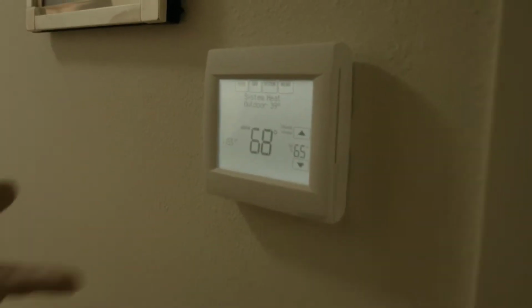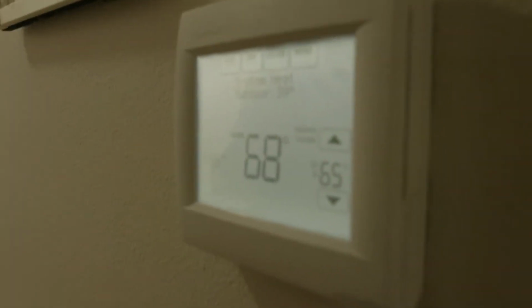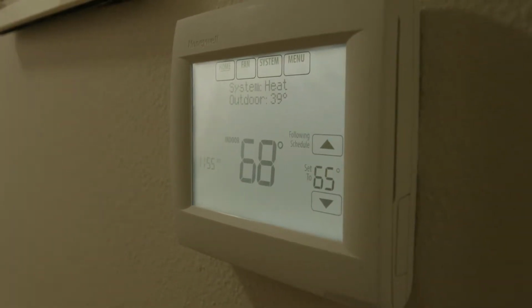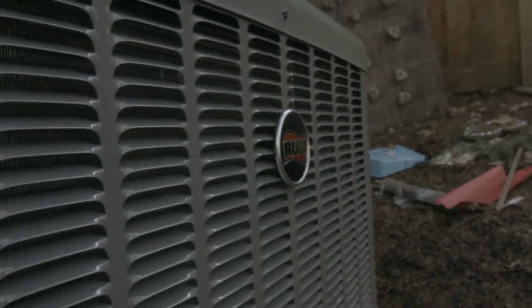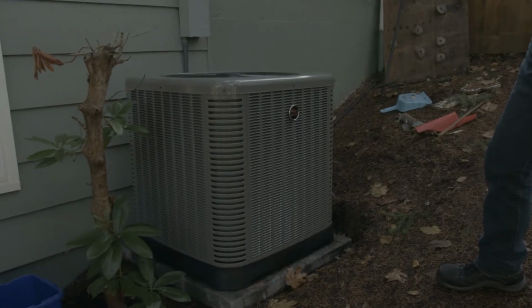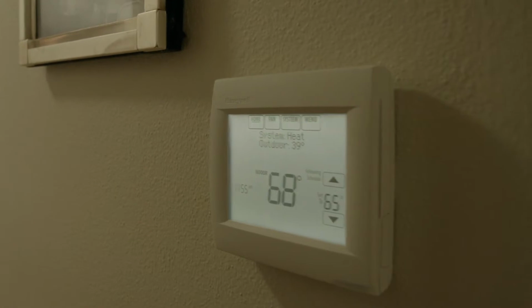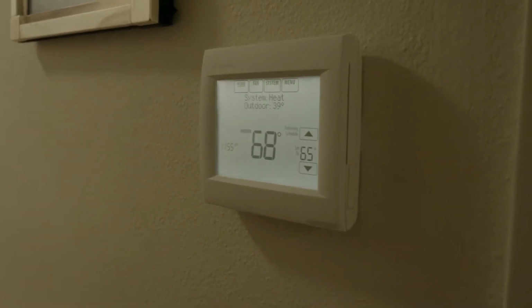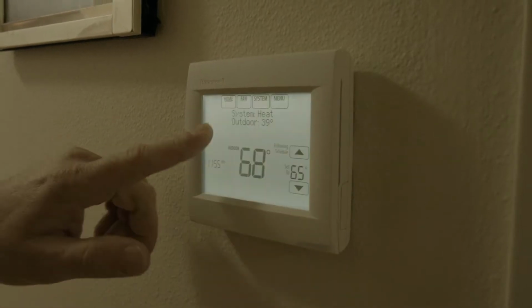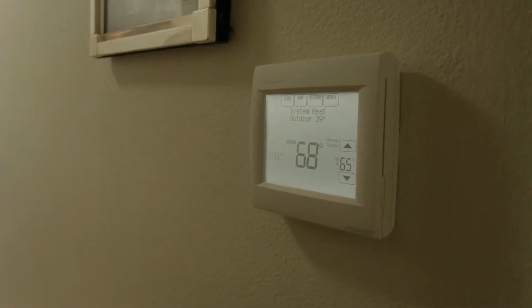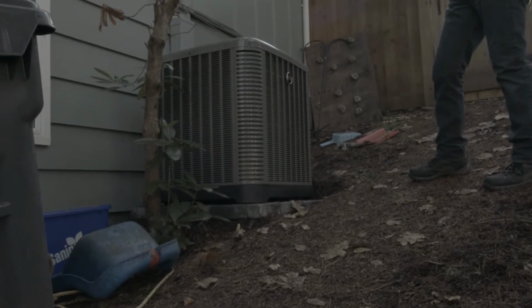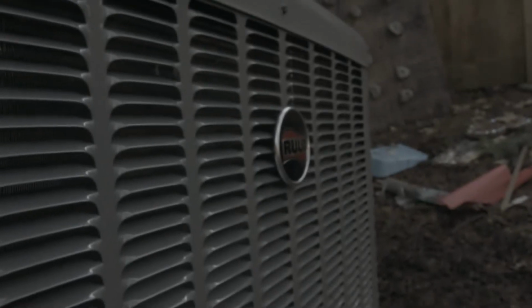The system is run by a Honeywell thermostat. There's also an outdoor sensor installed out by the heat pump that tells the thermostat what the outdoor temperature is. So this thermostat will always prioritize the heat pump over the heat strips. The heat strips are actually locked out above 30 degrees outside temperature. So pretty easy to operate thermostat. It's the little brain in the whole outfit. This is the heat pump that is connected to the air handler in the garage, and I might be biased, but I think Ruud equipment is the best looking equipment on the market.